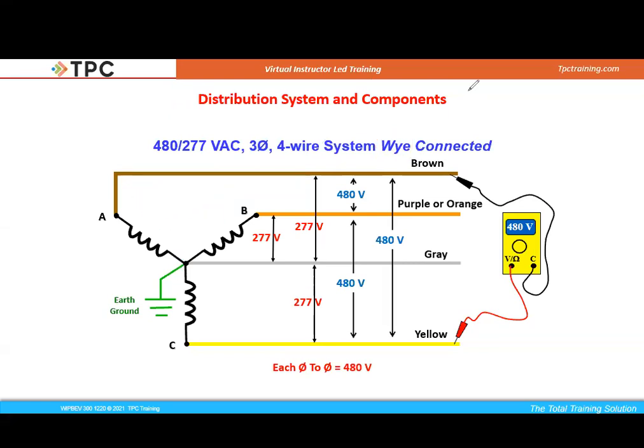So that's why we did that. And when these three energized conductors come into your facility, phase A, phase B, and phase C, we're going to bring them into some kind of distribution equipment. But eventually, they're going to get into a panel somewhere. And we're either going to have a main breaker in that panel or we're going to have main lugs only. But there's going to be three lugs that we're going to terminate phase A, phase B, phase C. And they would come directly into that panel. And so we'd be bringing in three phase, 480 volts, no doubt about it.